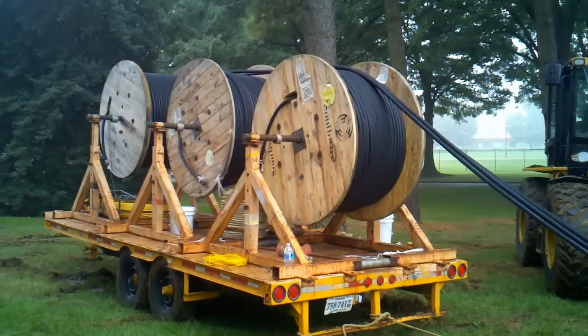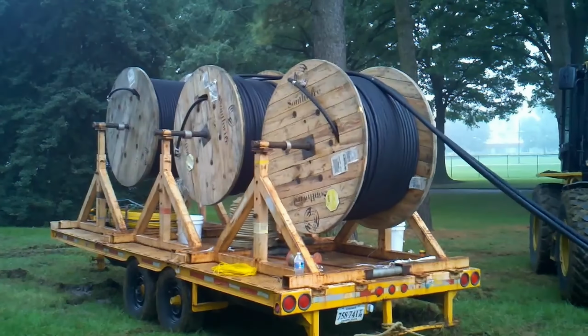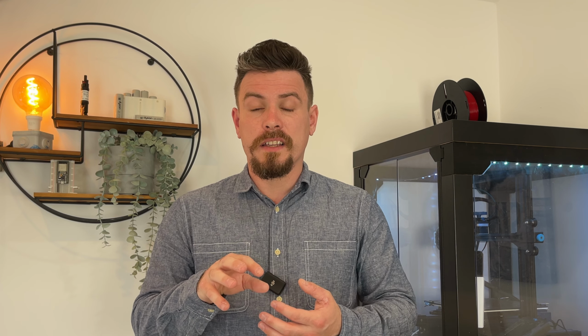Given that this is all theoretical and we're calculating these values to find our correct cable and breaker, we can use the values from the book rather than a physical test using a test device. We haven't got to drag 40 meters of cable out and then test it with the probes, have we? We're going to want to consider 4 things. The maximum permissible earth fault loop impedance, which will cause the device to act. Our actual earth fault loop impedance, the level of fault current that will flow under earth fault conditions, and finally, the disconnection time for the chosen protective device at that level of fault current to make sure that it will act within the time that it needs to.